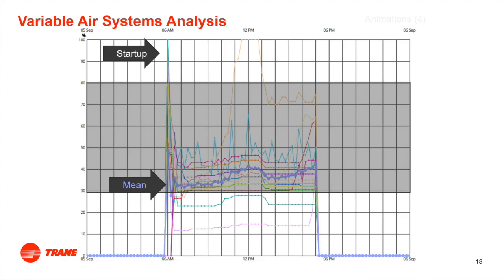Now, why do I care? If they're at the bottom of that control range, they tend to be noisy because they're starting to pinch down that air. And we see now, based on this chart, we've got outliers—those boxes we just saw in all that harvested data. We've got one that's open all the time, and a couple down here that are really closed out.